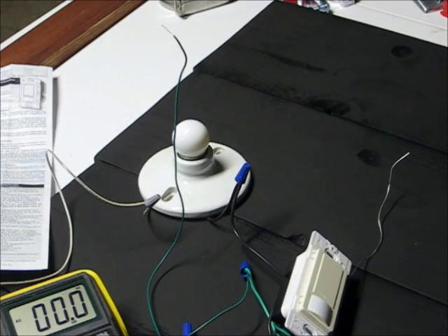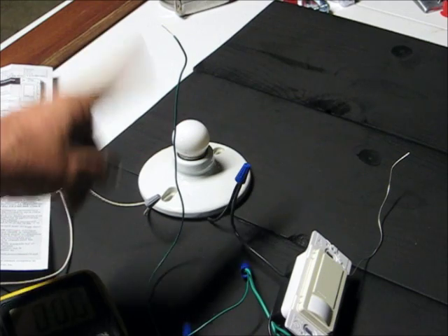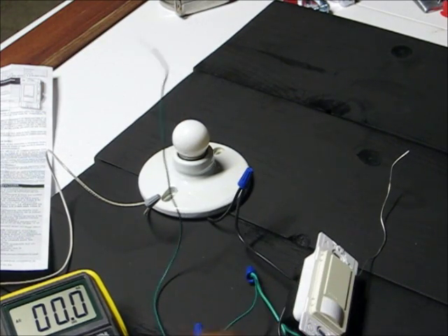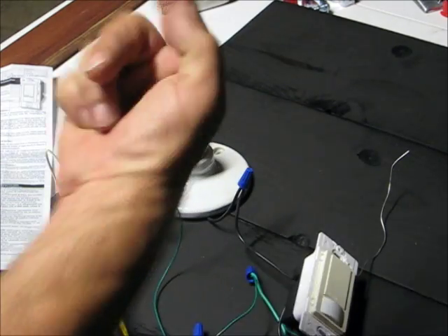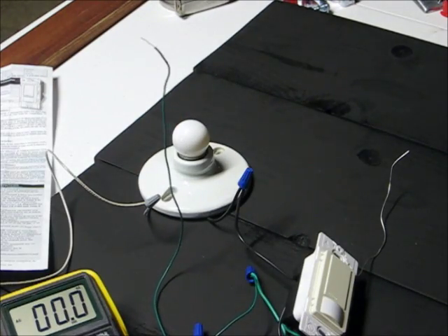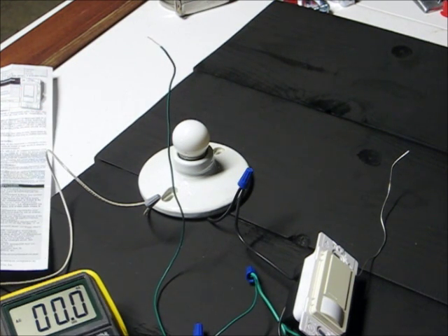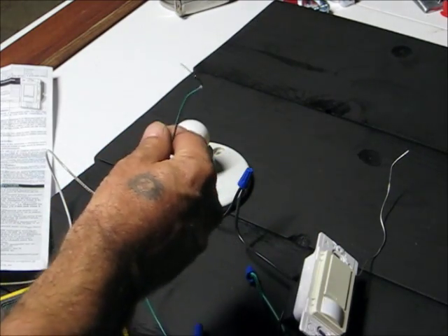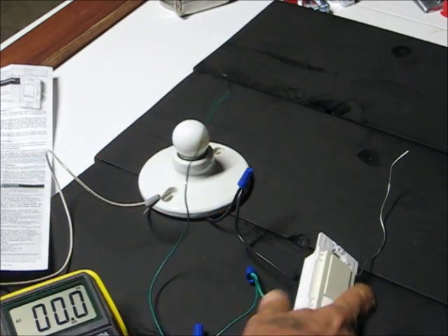With the ground wire disconnected and hanging up in mid-air, this unit no longer functions, because it's powered by a small amount of current coming through that wire, which means that wire is going to be sitting at line voltage, because you now have an open circuit. You can't use this device if you don't have a good ground. It will not function.